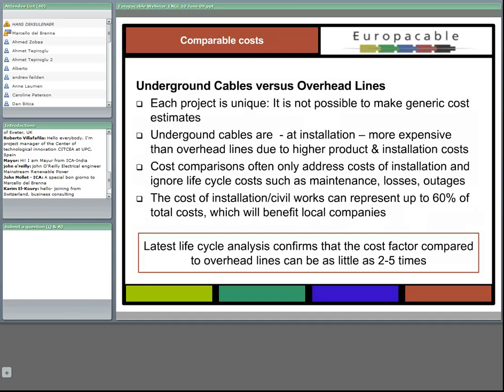It is sure that underground cables are more expensive to install than overhead lines. The product is more expensive since we're talking about insulated, screened and jacketed conductors rather than bare conductors, and installation costs are higher since we have to dig holes and trenches to install them underground. But if we consider other life cycle costs like maintenance, losses, and unexpected outages—even the brief outages present in overhead lines—the picture changes.